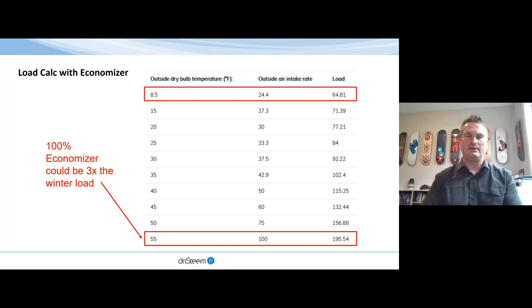So as I was mentioning, it's important to understand how much outside air we're going to use. So an example here, and if you're going to use economizer mode as well, we look at the outside air intake rate at 24.4. We look at a load of basically 65 pounds an hour for this example. It doesn't matter what part of the country or world we're looking at. This is just an example. But if we increase that air to 100% outside air, such as in an economizer mode, we've increased our load to almost 200 pounds an hour. So these are just factors that need to be considered.